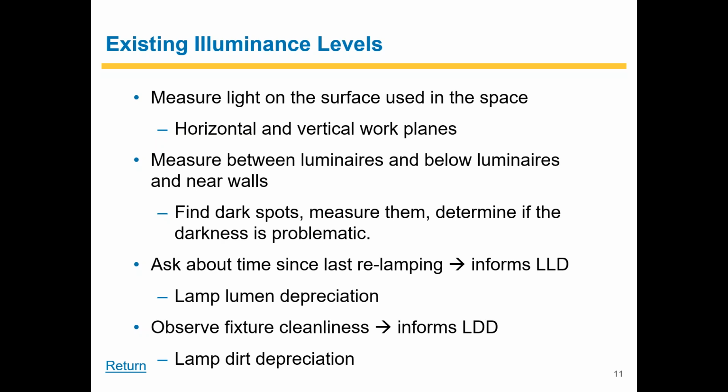Then, depending on how often you're running your lighting system, for an LED lighting product that runs continuously around the clock, after 8 years you're probably nearing 40-ish thousand hours, in which case we'd expect the lighting system to have lost about 20% of the lamp lumens that would otherwise be produced for an LED product. So keeping these ideas in mind and designing as appropriate is going to make sure that you head off any problems down the line.